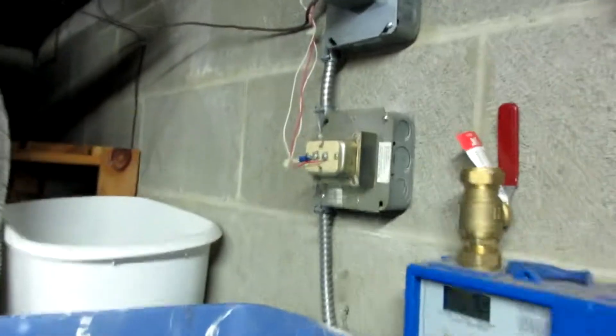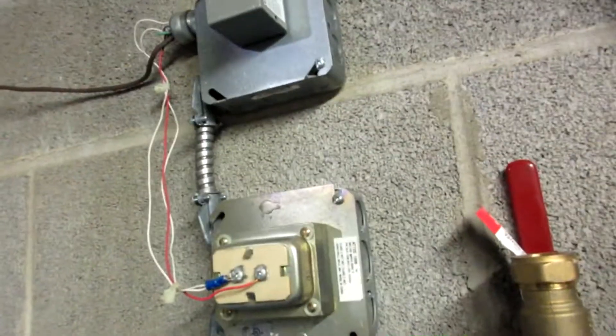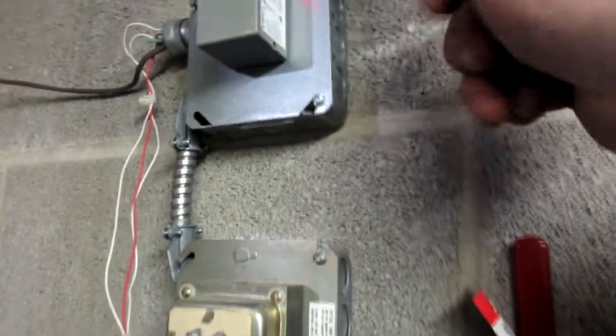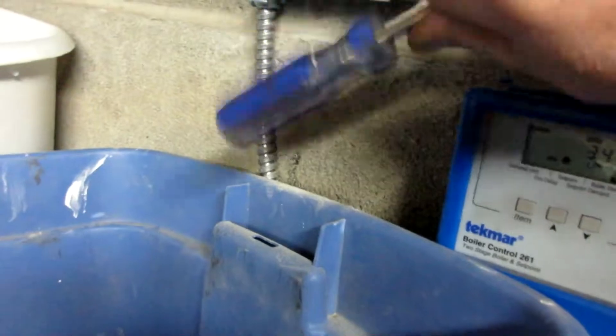So I'm thinking about the low voltage thermostat wires — white and red, white and red. I started tapping on this connection block and a bunch of white dust fell out of it. I tapped on it and it tried to start, and it started.